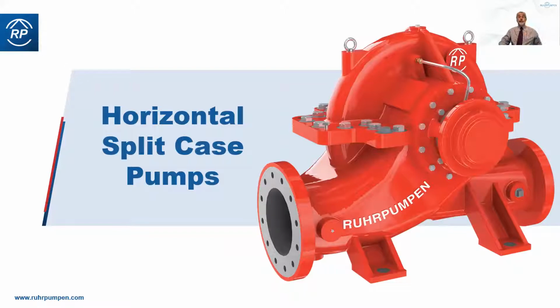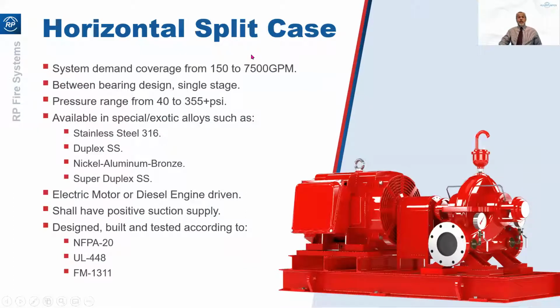So looking first at the horizontal split case pumps. Here's the approximate coverage range and pressure range. Now, the standard material for a fire pump would be cast iron, bronze fitted. So that's cast iron casing, bronze wear rings, bronze impeller, stainless steel shaft. That will be the standard FM approved UL listed materials. They are available in other materials, but they're not as such UL FM listed in these materials, but they could be on an individual case-by-case basis. A few $1,000s and a few months lead time would be required to elevate a pump to that level.